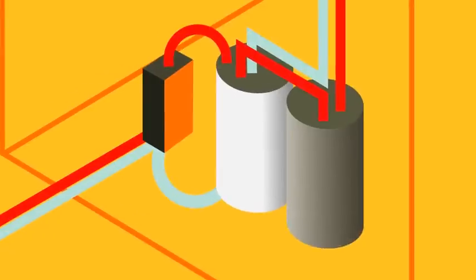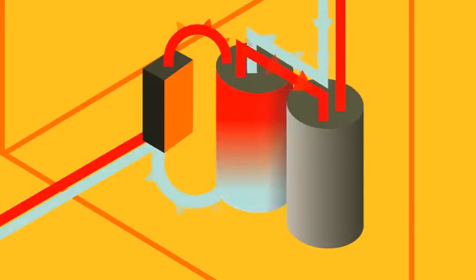Sunward solar storage tank is connected into your existing hot water system with another set of flex hoses. Cold water from your well or city water supply goes into the bottom of the solar tank. Solar heated water comes out of the top of the tank and into your existing water heater.